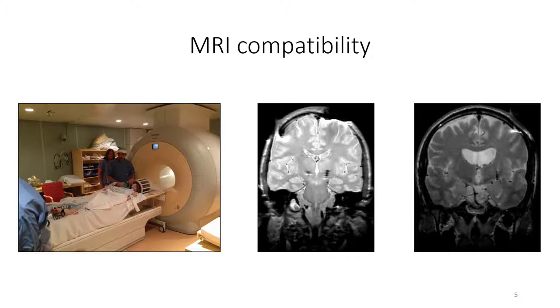As I see it, the only real disadvantage with hybrid systems is that they are not what is called MRI compatible. However, often an MRI can be replaced with another investigation, such as CT. Further, the hybrid system is in reality not MRI incompatible. The compatibility has not been tested and is not guaranteed by the manufacturer, and this is by many understood as the system being incompatible with MRI and that MRI is impossible to perform. In reality, there is every reason to expect these to be compatible.